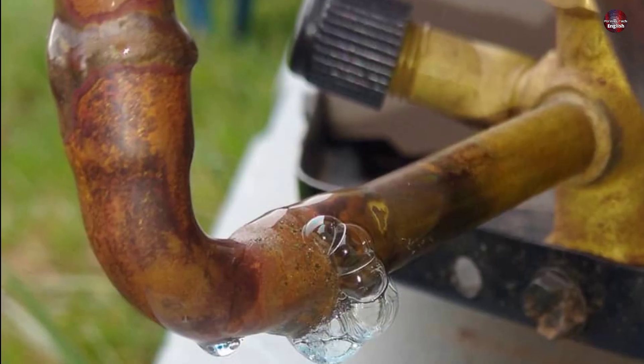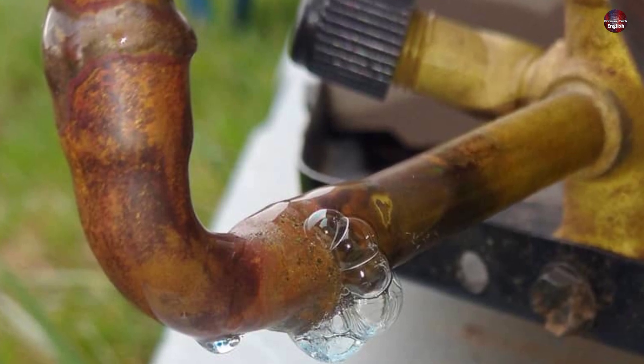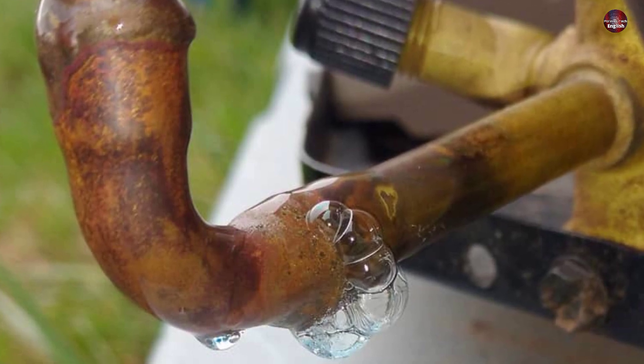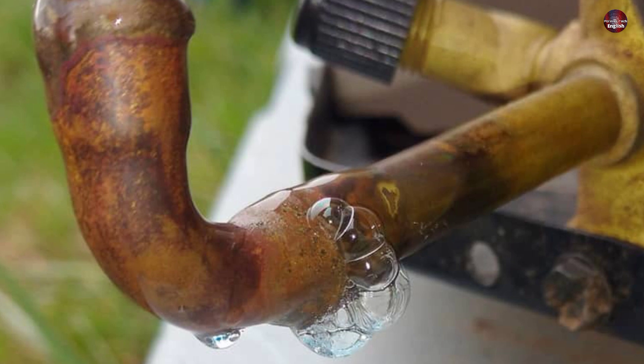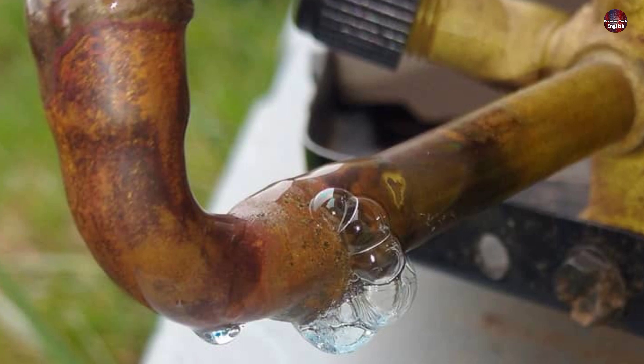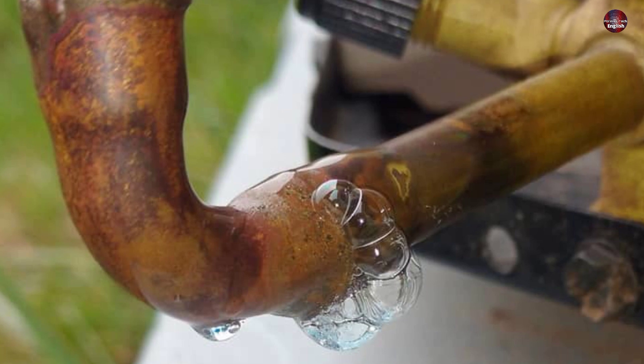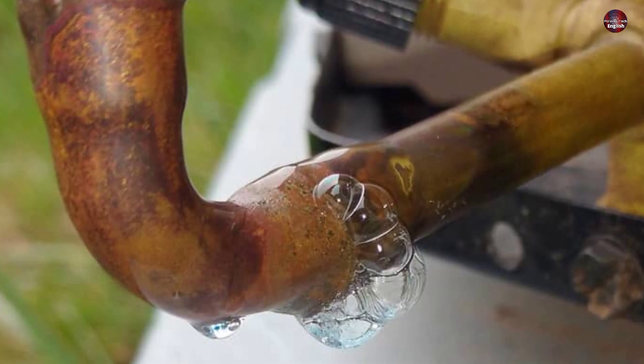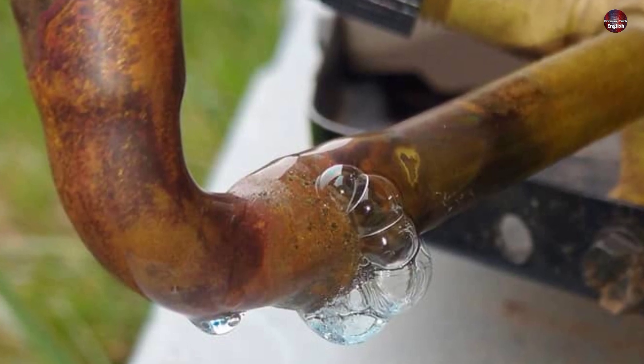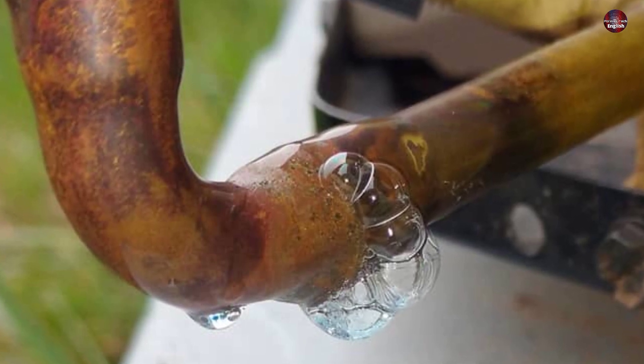If the refrigerant leaks out of the unit, the H3 error code will also be displayed on the indoor unit. When the air conditioner is working normally with refrigerant filled inside, the suction line cools itself and also cools the evaporator. When refrigerant returns through the suction pipe, it is still quite chilled, and this cooled refrigerant helps the compressor maintain normal temperatures. When the gas leaks, no cool refrigerant flows inside the suction line, which makes the compressor heat up, and thus the H3 error will be shown.